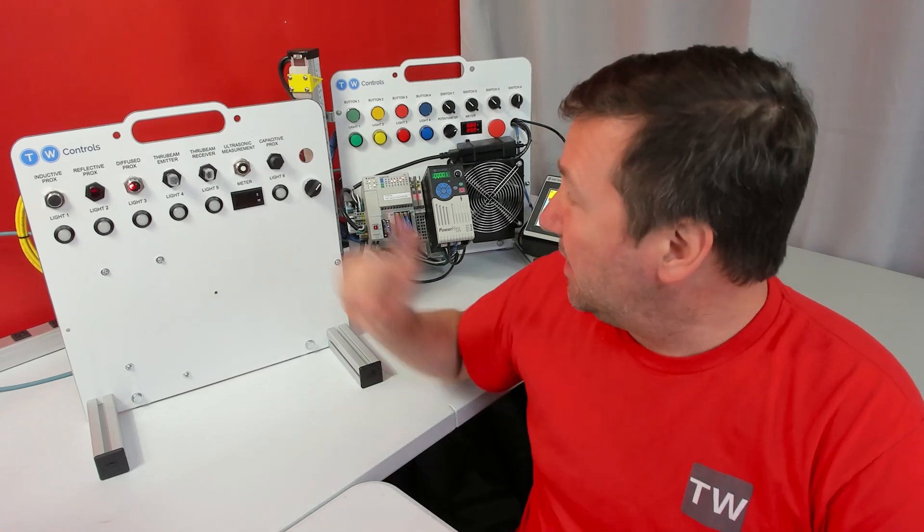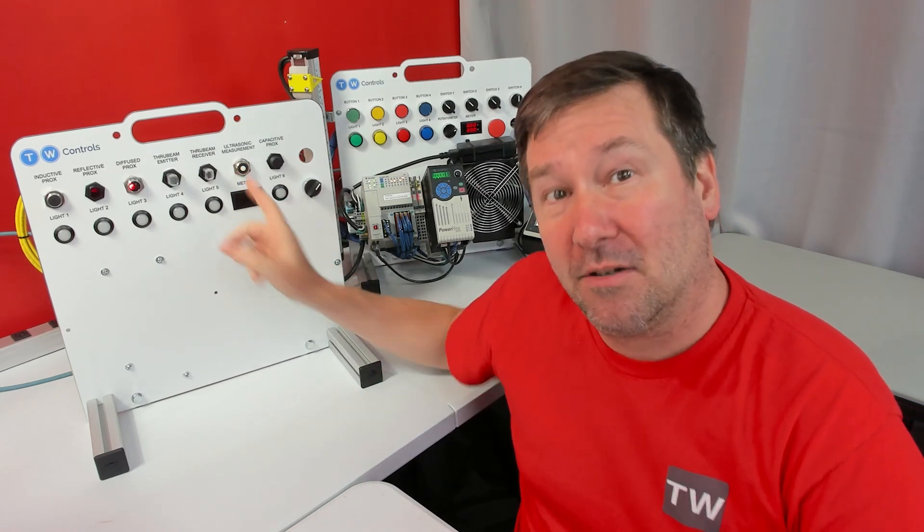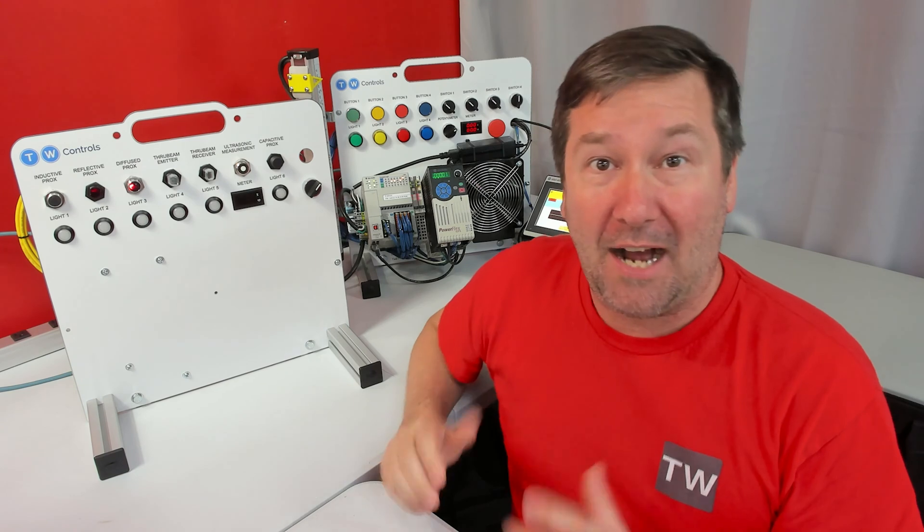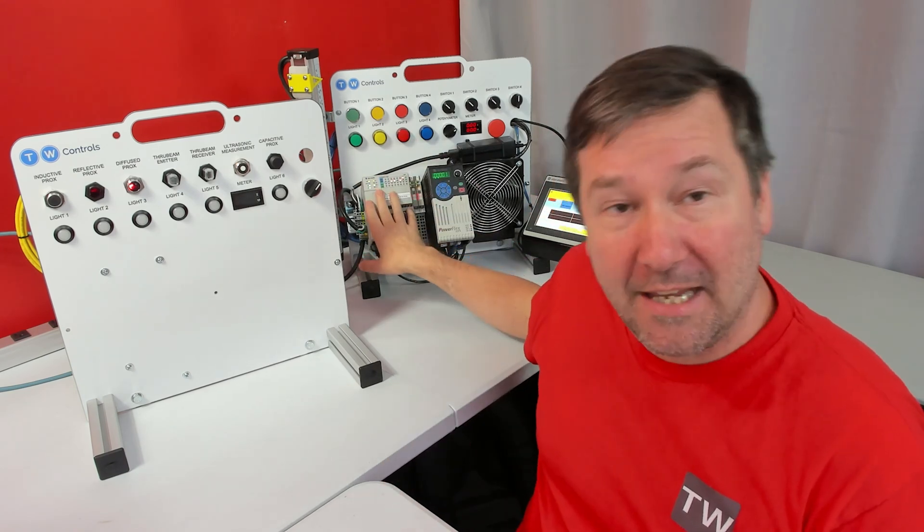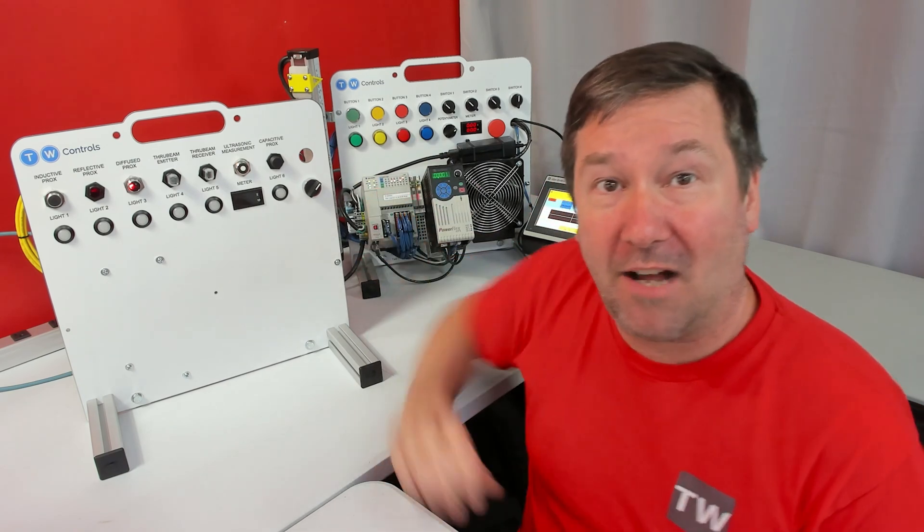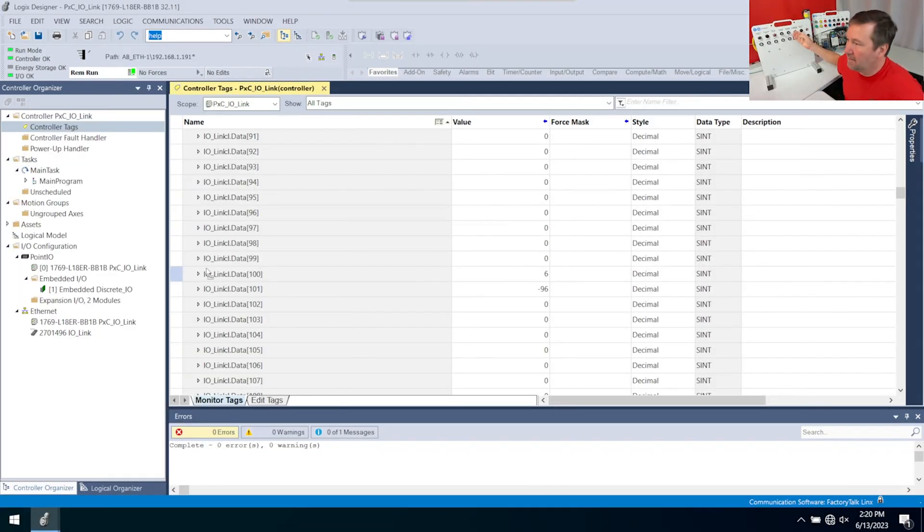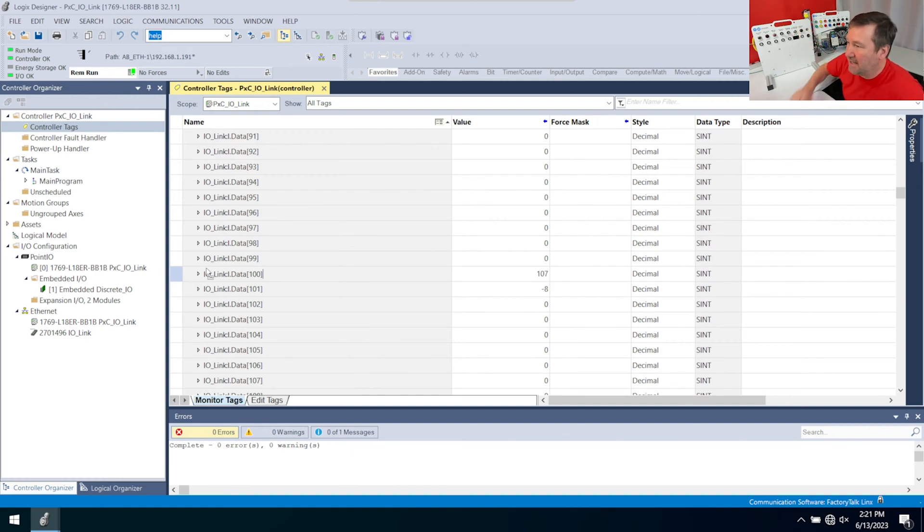In previous videos, we connected our ultrasonic 4 to 20 milliamp signal to IO-Link and configured it in the CompactLogix in Studio 5000. It's coming across in two small integers. As I move my finger across the ultrasonic sensor, you see both of these are changing.